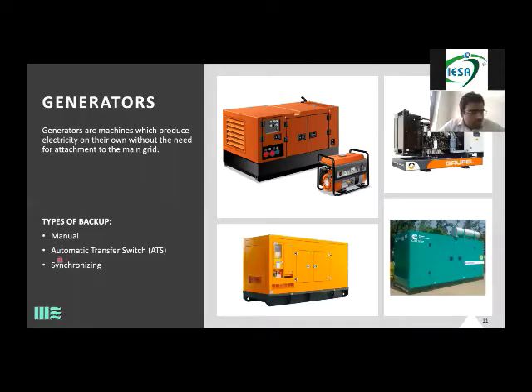The third is synchronization. So what is synchronization? In the case of manual and automatic, as I told you, the main genset is running on load and the other ones are just idle, what we call hot backup. In synchronization, they share the load. If 3 gensets are running in synchronization and the load is maybe 240 kilowatts, they are running at 80, 80, 80. So they are sharing the load amongst each other.